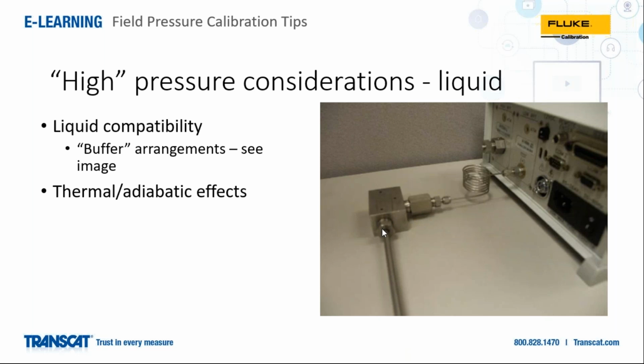And in this fitting, you would push fluid out from the device under test or from the standard, either direction. This buffer tube here is already filled with the fluid that this instrument takes, and this union, this intermixing point here, forms a fluid buffer.